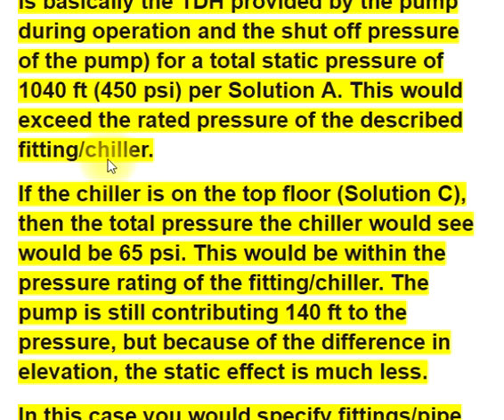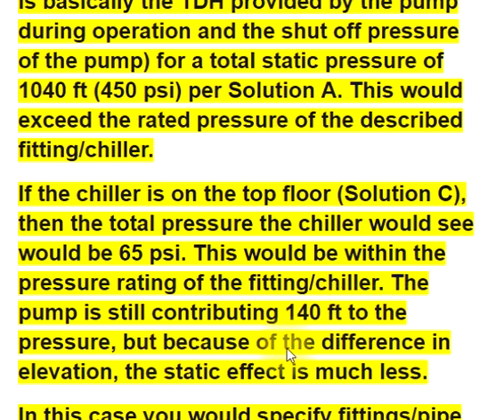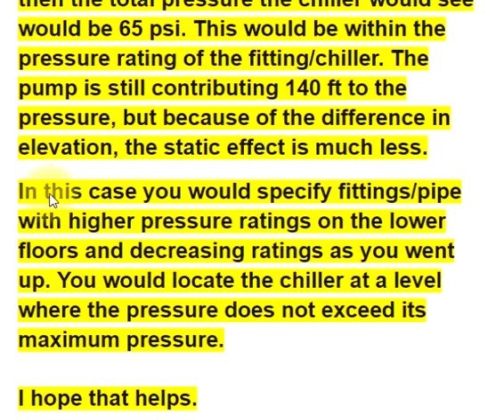If the chiller is on the top floor (solution C), the total pressure the chiller would see would be 65 psi, which would be within the pressure rating of the fitting and chiller. The pump still contributes 140 feet to the pressure, but because of the difference in elevation, the static effect is much less. In this case, you would specify fittings and pipes with higher pressure ratings on the lower floors and decreasing ratings as you go up, and locate the chiller at a level where the pressure does not exceed its maximum rating.